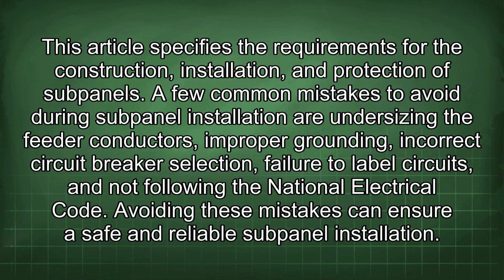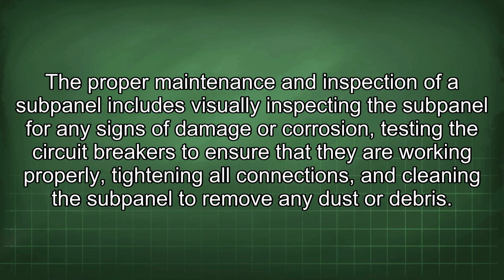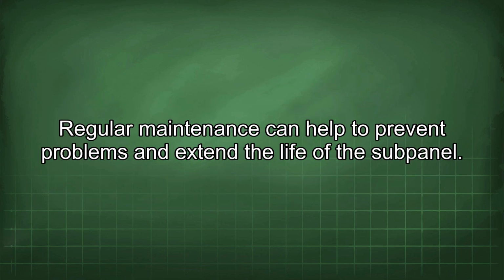A few common mistakes to avoid during subpanel installation are undersizing the feeder conductors, improper grounding, incorrect circuit breaker selection, failure to label circuits, and not following the National Electrical Code. Avoiding these mistakes can ensure a safe and reliable subpanel installation. The proper maintenance and inspection of a subpanel includes visually inspecting the subpanel for any signs of damage or corrosion, testing the circuit breakers to ensure that they are working properly, tightening all connections, and cleaning the subpanel to remove any dust or debris. Regular maintenance can help to prevent problems and extend the life of the subpanel.